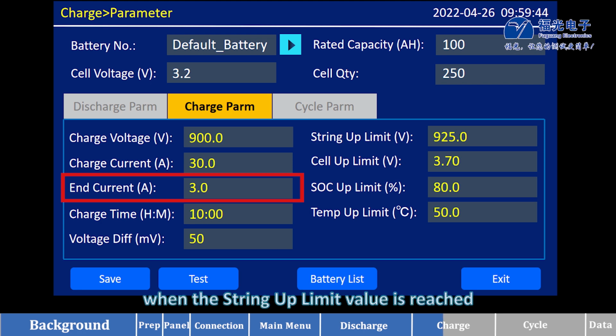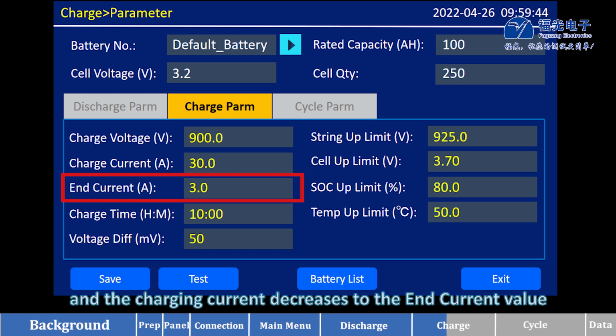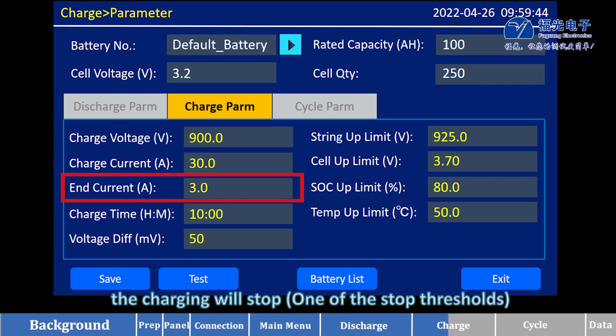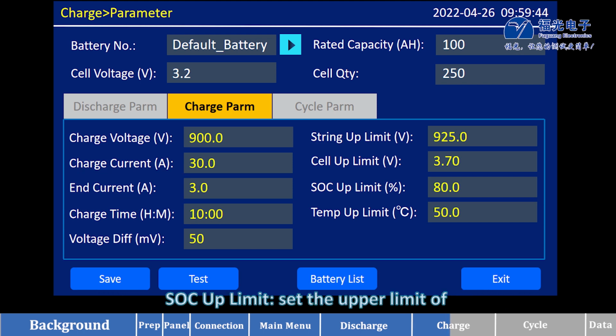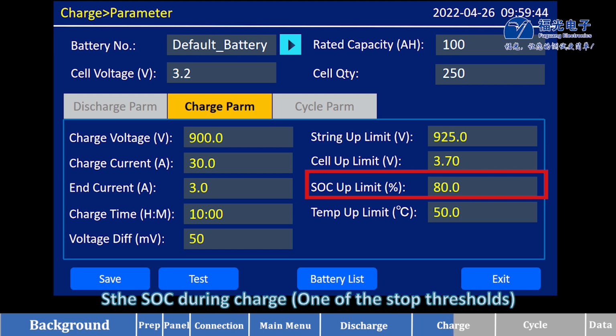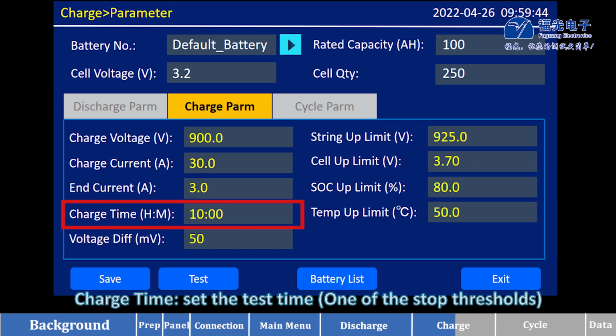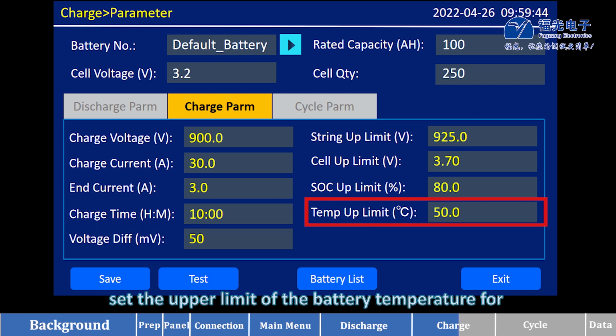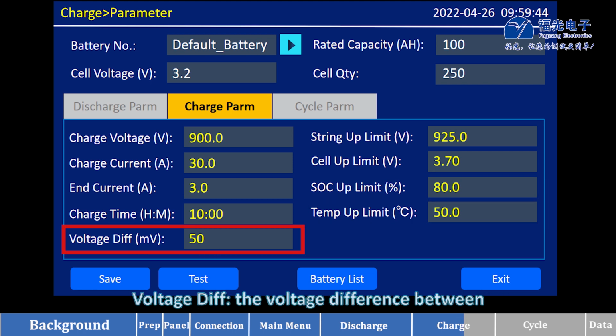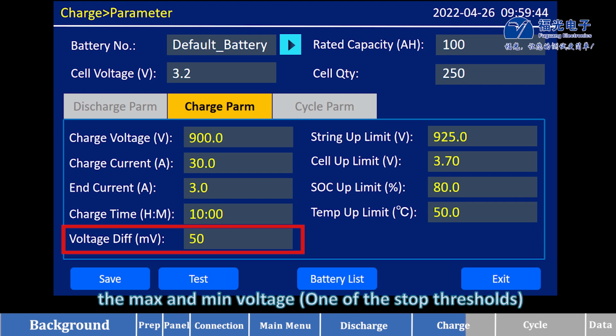End current. When the string up limit value is reached and the charging current decreases to the end current value, the charging will stop. SOC up limit. Set the upper limit of the state of charge during charge. Charge time. Set the test time. Temp up limit. Set the upper limit of the battery temperature for over temp protection. Voltage difference. The voltage difference between the maximum and minimum voltage.